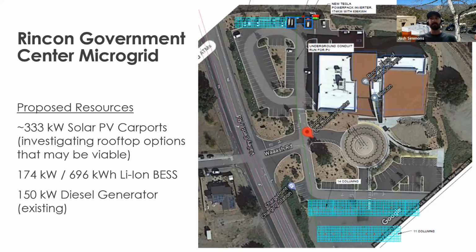But you would want to ensure that as part of that initial contract for installation, you have an inclusion of some operations and maintenance training, at least basic, even if you do have an O&M provider, so you have an understanding of the system and how to monitor it. And ultimately, ideally, you're having a 5 to 10 year plus plan with renewable terms on operations and maintenance by a third party that's going to come out and keep these systems optimally functioning, or at minimum, at least remotely monitoring them. Because then, through the remote monitoring of their performance, of their inverters, you can see, this is the expected production and this is what it's actually doing.